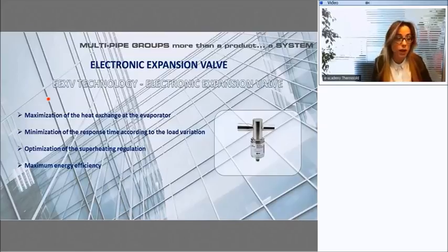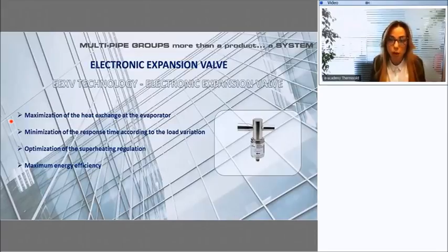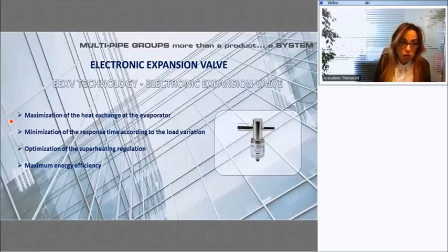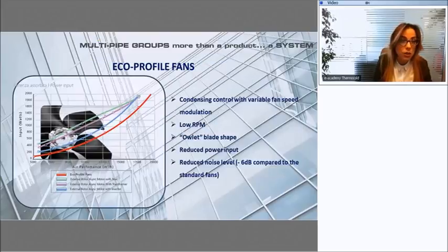Let's analyze now in detail the single components of the unit. The unit is equipped with eco-profile fans, and all the fans are regulated with a step condensing control in order to ensure the proper adjustment of the airflow in accordance to the different outdoor air temperature. We have, of course, two plate heat exchangers, one dedicated for hot water and the other dedicated for chilled water. Scroll compressors from Danfoss.